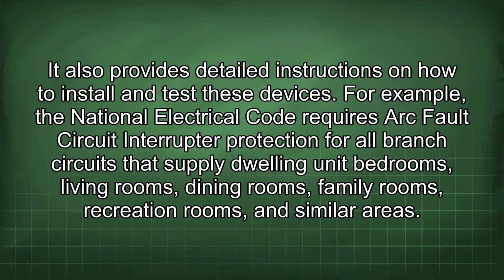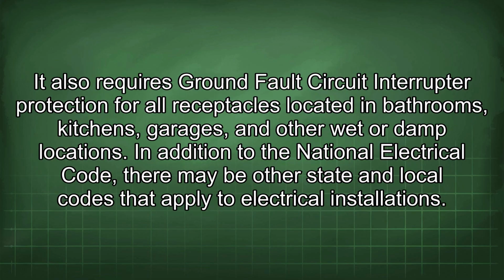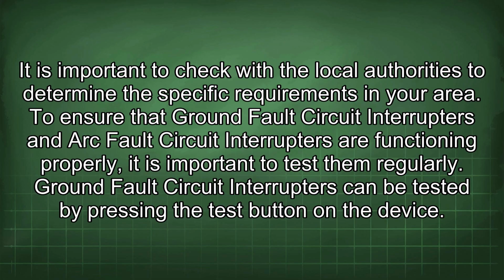For example, the National Electrical Code requires arc fault circuit interrupter protection for all branch circuits that supply dwelling unit bedrooms, living rooms, dining rooms, family rooms, recreation rooms, and similar areas. It also requires ground fault circuit interrupter protection for all receptacles located in bathrooms, kitchens, garages, and other wet or damp locations. In addition to the National Electrical Code, there may be other state and local codes that apply to electrical installations. It is important to check with the local authorities to determine the specific requirements in your area.